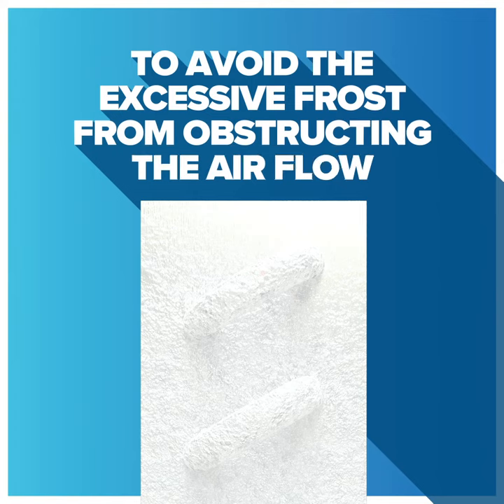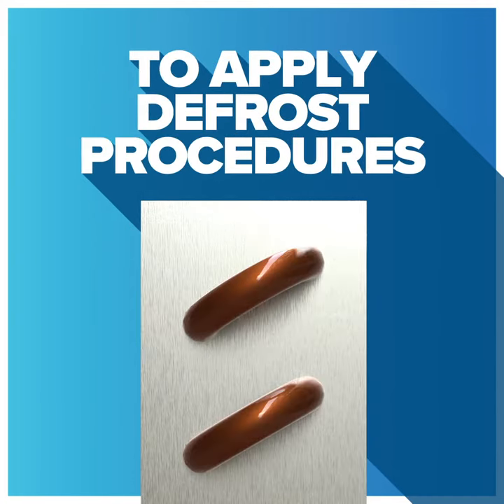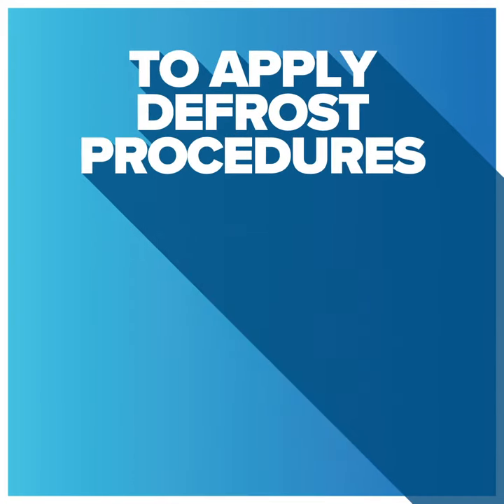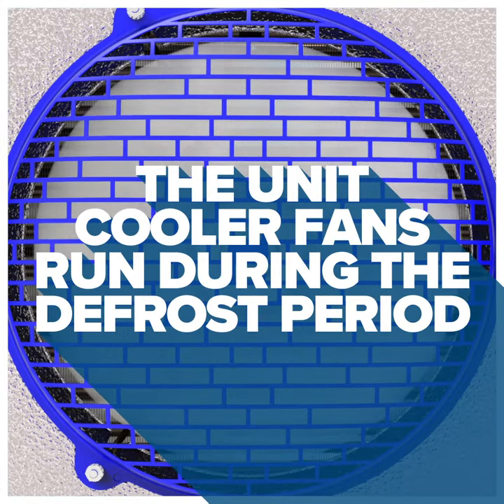To avoid excessive frost from obstructing the airflow through the evaporator coil, the system stops the compressor and outdoor fans periodically to apply defrost procedures. This is air defrost. During this type of defrost, the unit cooler fans run during the defrost period.